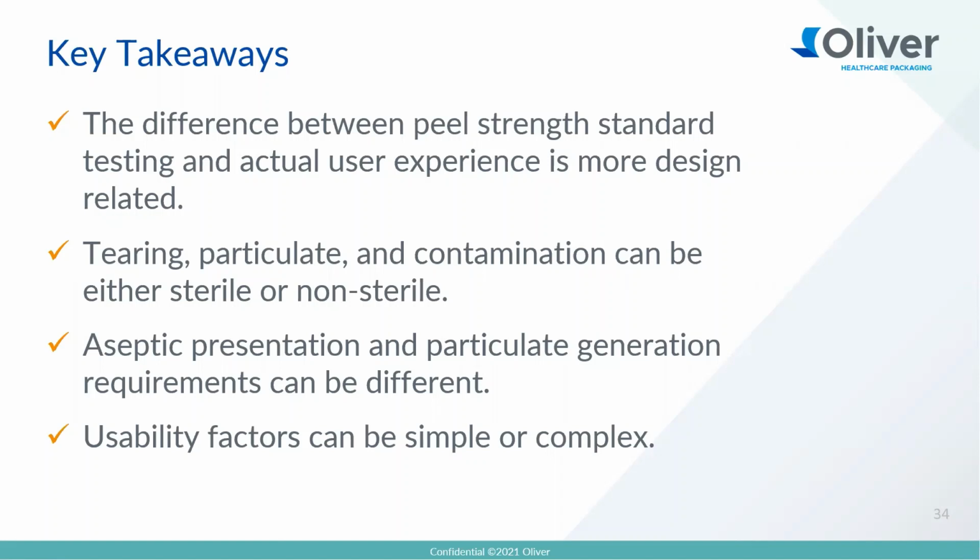And then finally on to the usability factors. They can be simple or they can be very complex. I suppose it's really down to the end user. So during the device design validation, that's the time to assess package usability, and that's the time to bring in the human factors consultants, belts and braces, to make sure everything is what you intended it to be. And then also to complete the formative and summative studies, to ensure that what you've selected actually meets form, fit, and function.